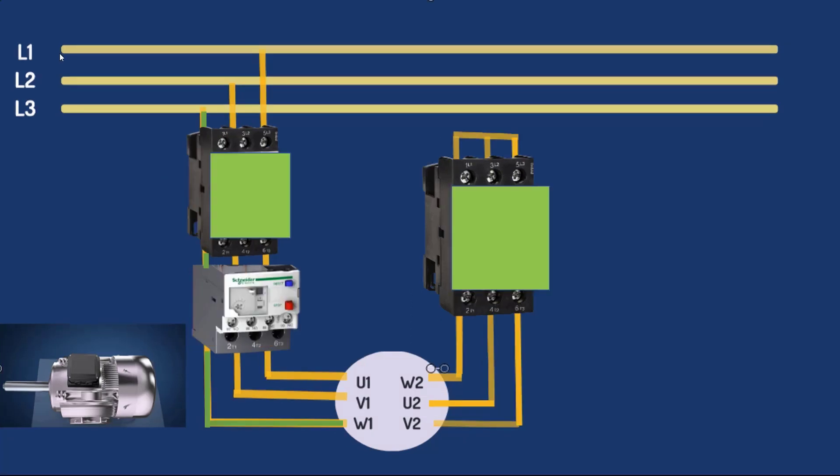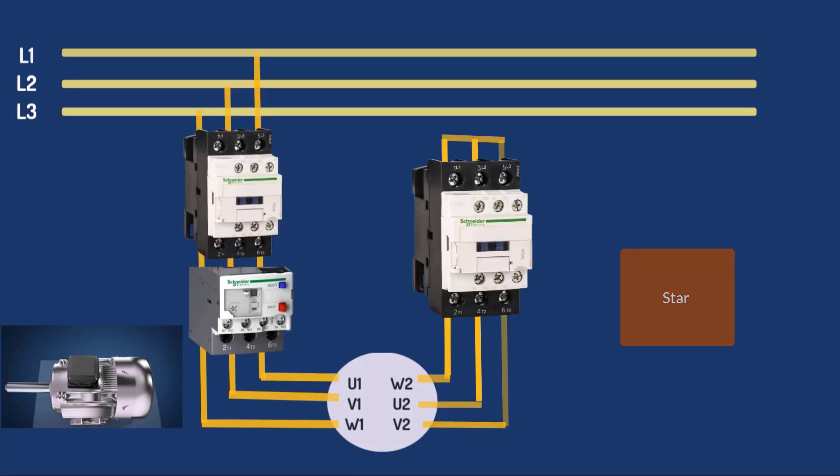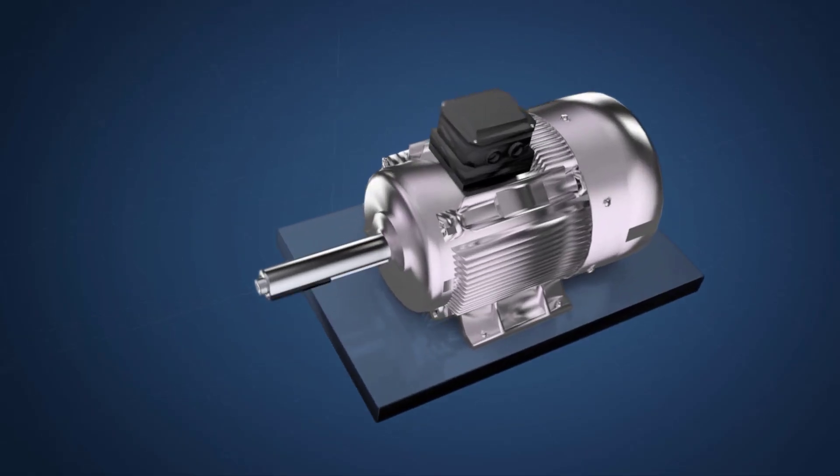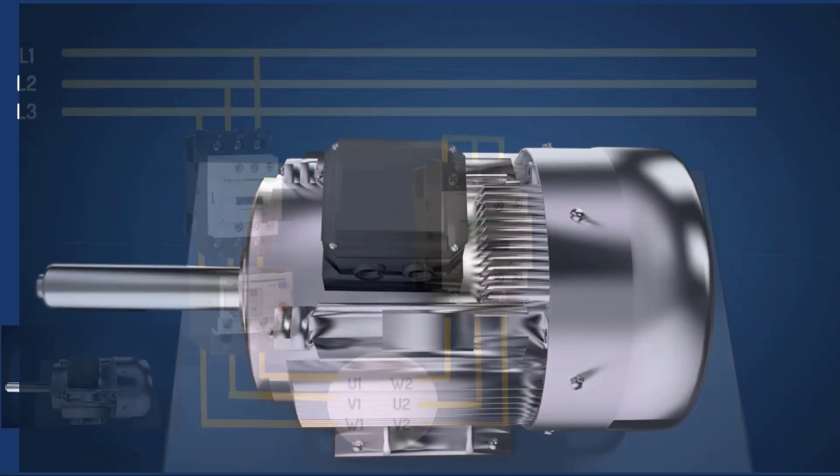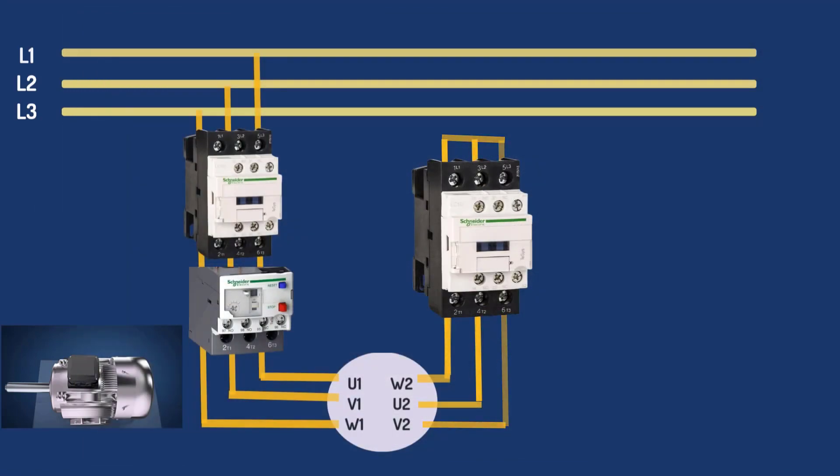When the main contactor and star contactor are energized, the motor will run in star connection. Around 58 percent of the coil voltage is used when using star configuration compared to delta configuration. When the motor starts in star, there is less current in the coil which results in a drop in torque output. When the motor attains 90% of full RPM, a timer connected in the circuit is activated. It disconnects the star contactor first and connects the delta contactor into the circuit.